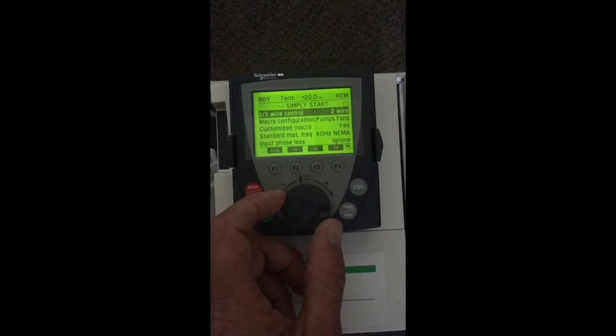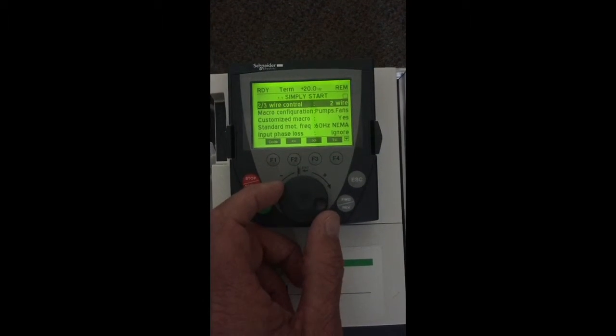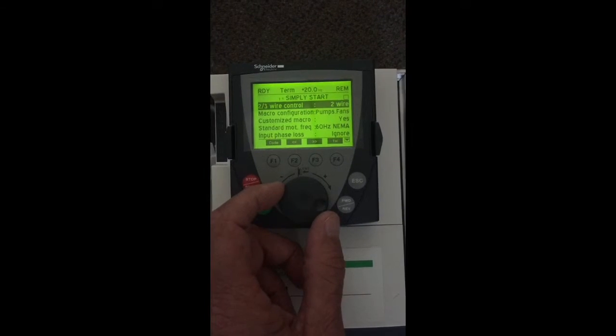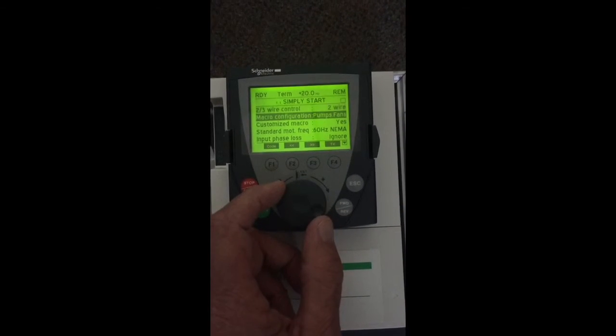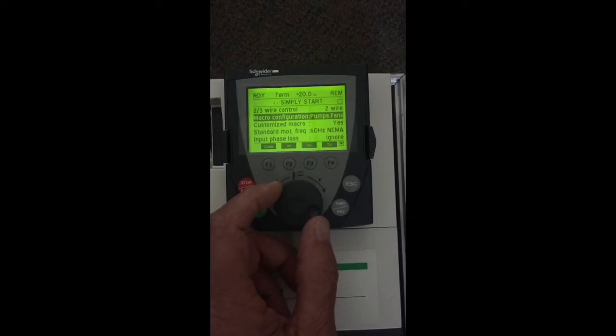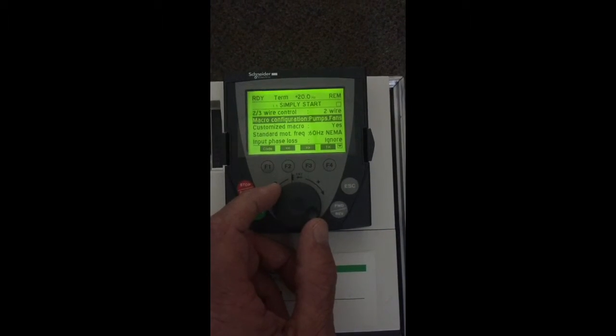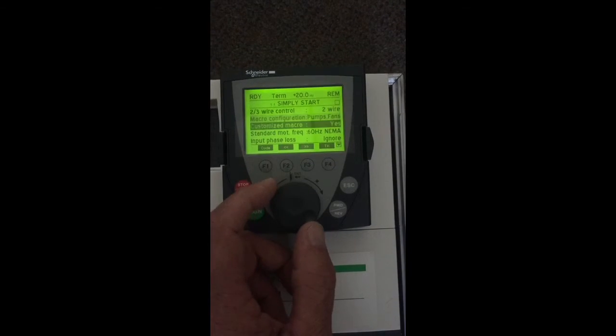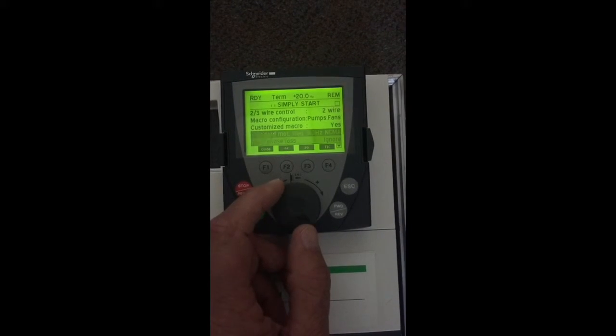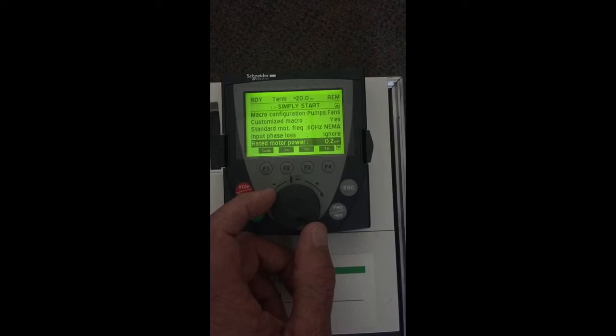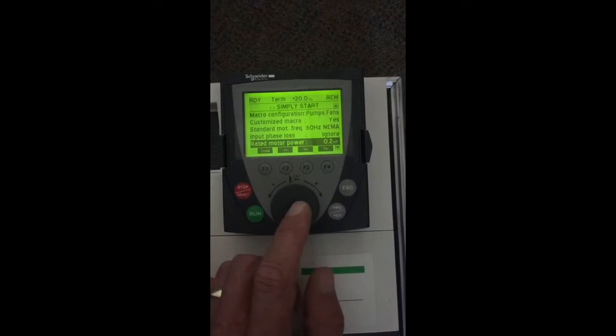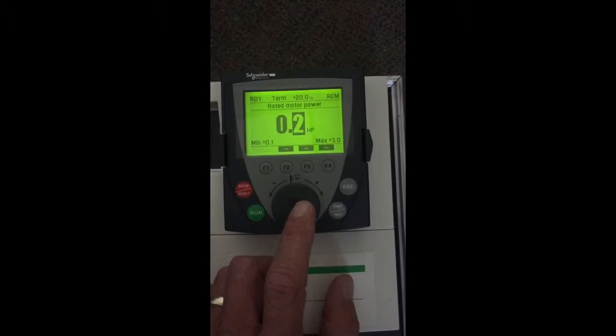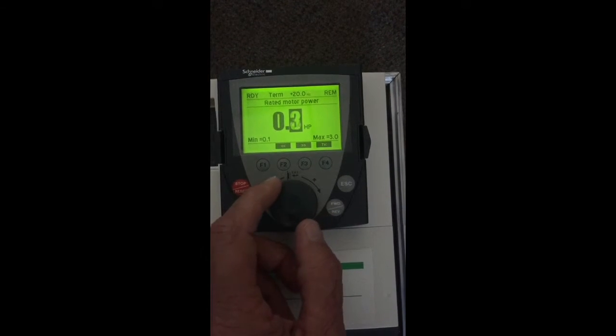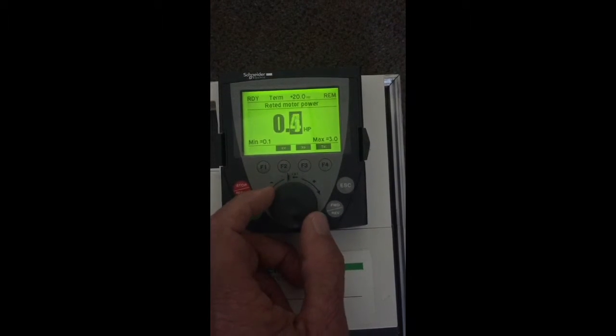As you scroll through, you'll see your basic parameters for your controls. Configuration for pumps and fans already pre-configured for the drive. We will scroll through to our motor parameters. Here's where you'll set your horsepower. Enter in to adjust. Simply rotate the dial.